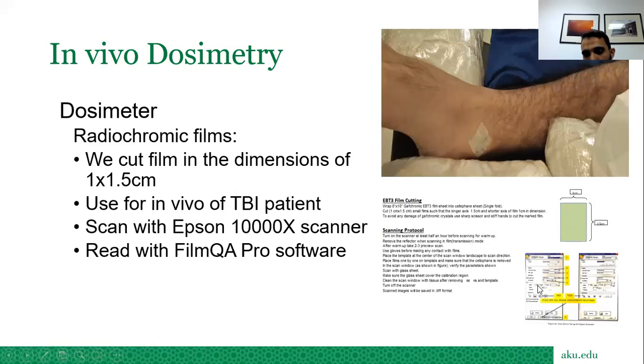Films are read using FilmQA Pro software. We first generate a calibration curve by exposing films to known doses. The calibration chips range from zero (background) through doses of approximately 52.9, 71.7, 103.8, 145.5, 203.77, 285, and up to 398.8 cGy, producing corresponding optical density (blackening) values. Optical density indicates the degree of film blackening as a function of dose.